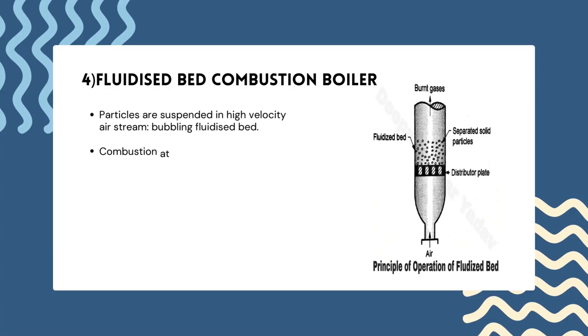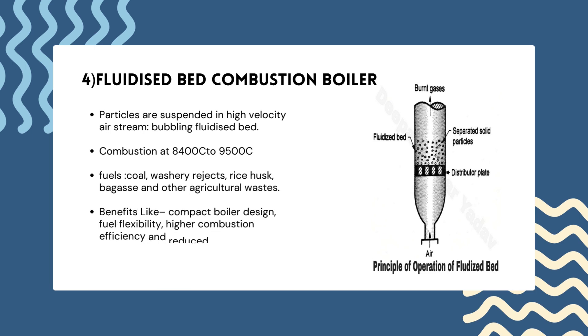Fluidized bed combustion boilers have emerged as a viable alternative with significant advantages over conventional firing systems. They offer compact boiler design, fuel flexibility, higher combustion efficiency and reduced emissions of noxious pollutants such as sulphur oxides and nitrogen oxides. Fuels burned include coal, washery rejects, rice husk, bagasse and other agricultural waste. Capacity ranges from 0.5 to over 100 tons per hour, with combustion occurring at 840 to 950 degrees Celsius.